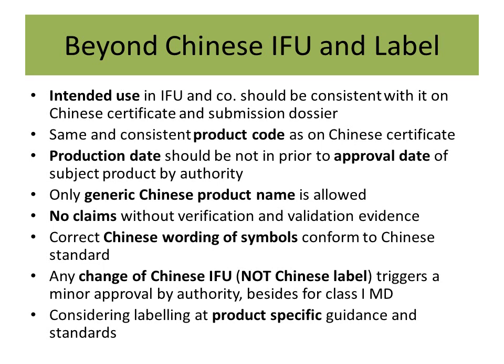In China, the international symbols will be more recognized with fixed Chinese wording. If you change Chinese IFU of Class 2 and 3 medical device, you have to apply for a minor registration. Like for Chinese regulation, you have to follow the similar product-specific guidance and standards with labeling chapter as life learning. The labeling is also stipulated there.